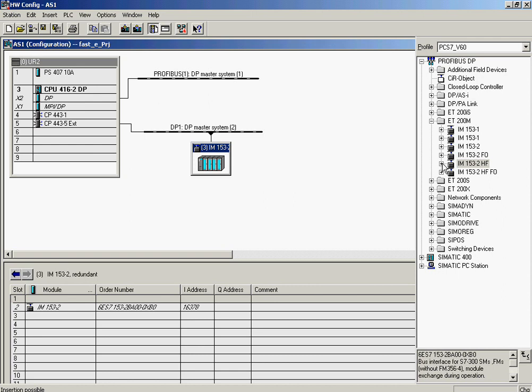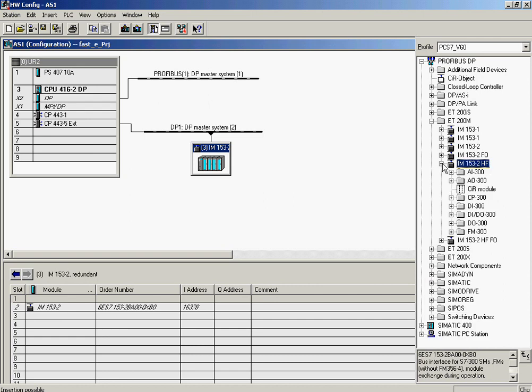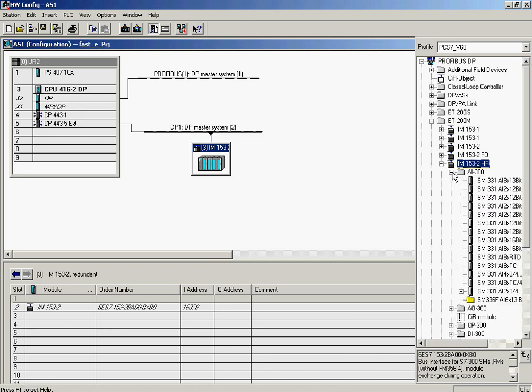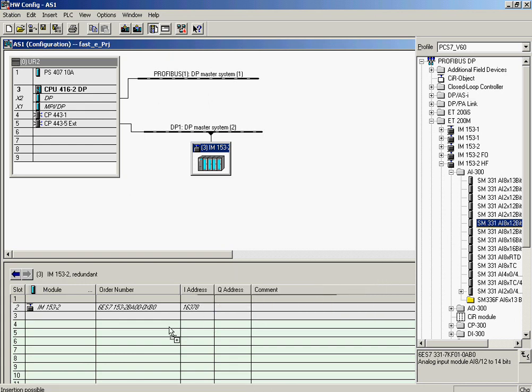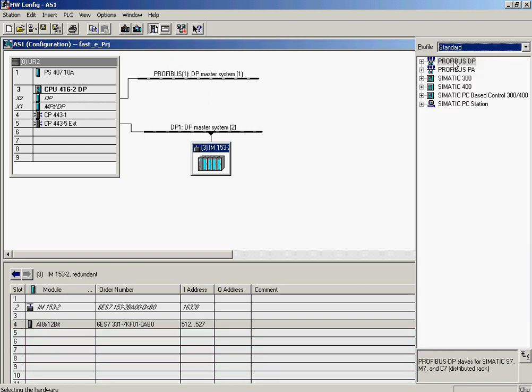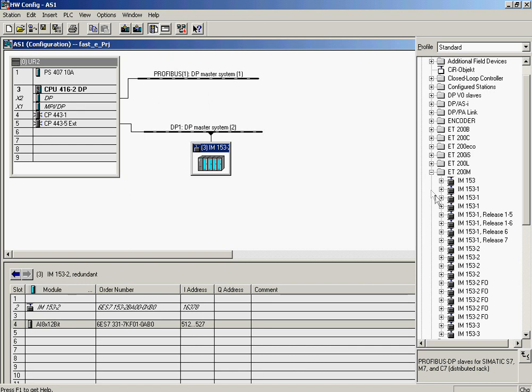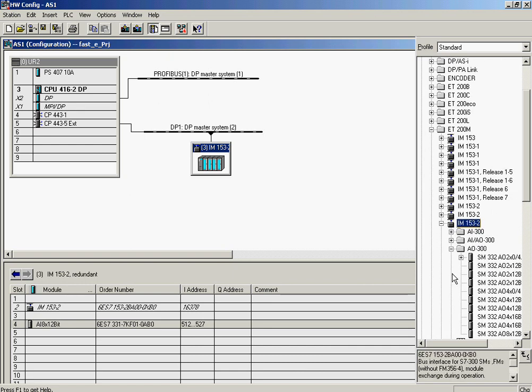The ET200M is equipped with an analog input, an analog output, a digital input, and a digital output, which will all be configured. The analog input module is plugged into slot 4. This module is included in the catalog of hardware optimized for use with PCS7 V60. The analog output module is plugged into slot 5, from the standard hardware catalog, which contains all modules supported by and compatible with SIMATIC PCS7.